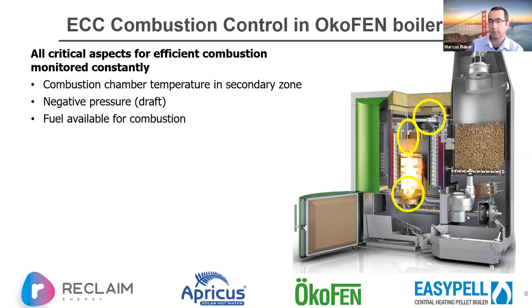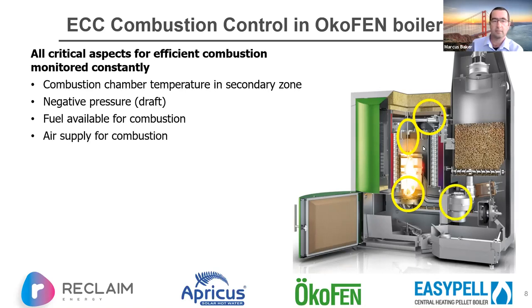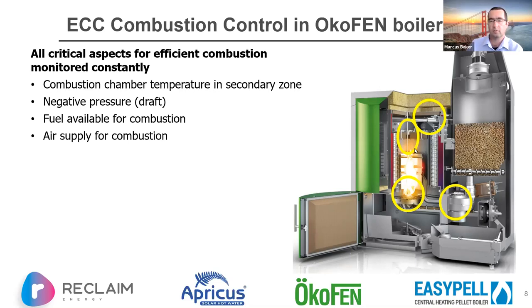Fuel is constantly fed in through an auger system into the bottom-fed grate via the day hopper. The balance of temperature, fuel, and air gives you controlled air in and air out. In the Ökofen system the combustion chamber is a gas-sealed unit — the only air able to enter is through the fan system, which is entirely controlled. By knowing and controlling fan speed and monitoring the negative pressure from draft, the boiler has a very good idea of how much air is available.